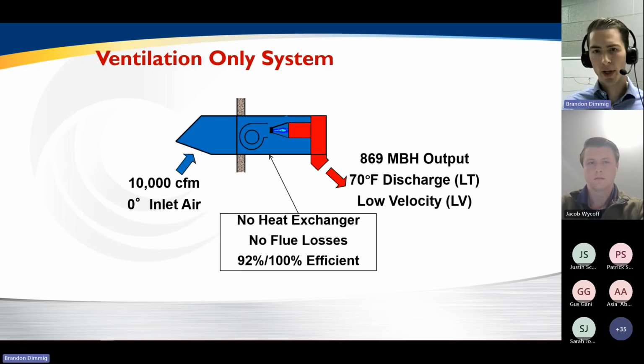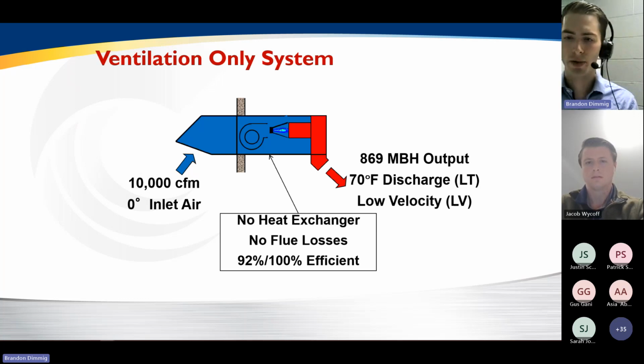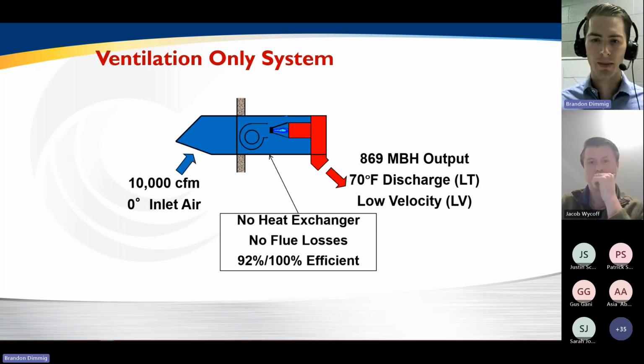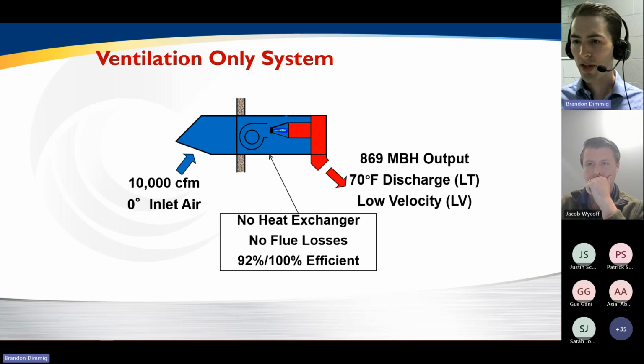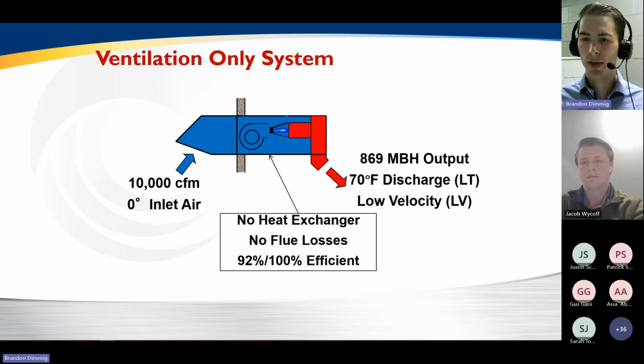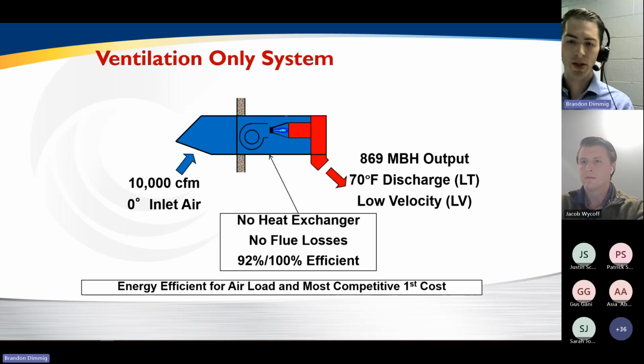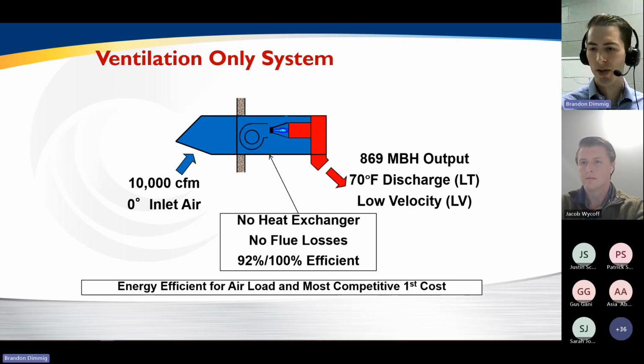So practically, if we're just looking at the ventilation load right now, just the air load, take a theoretical 10,000 CFM direct fired unit. You bring in 0 degree air, you heat it up to 70 degrees. This is roughly an 870 MBH output unit. But again, no flue losses, no heat exchanger losses. It's going to be 92% thermally efficient. This is the most energy efficient and competitive first cost way to heat the air load of a building.